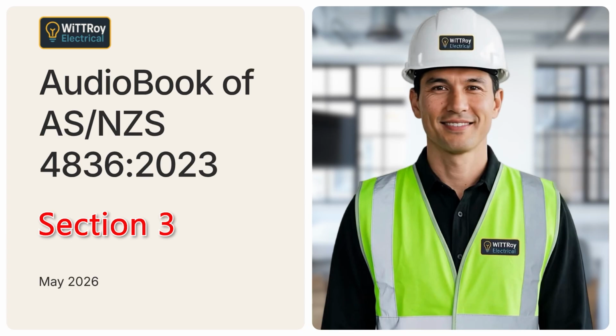Clause 3.1.3. Isolation of electrical equipment. Clause 3.1.3 explains how electrical equipment must be isolated. The electrical equipment to be worked on must be isolated from all sources of electrical supply. This may be done by opening switches, removing fuses or links, opening circuit breakers, or removing circuit connections.